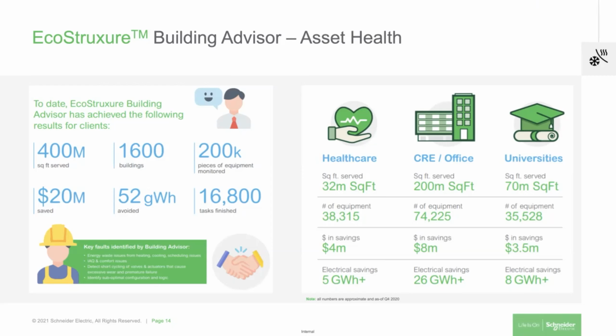Next question: how do you calculate energy savings? Within our fault detection and diagnostics, we have mechanical schedules—the ratings of the pumps, the flow rates, the size of the mechanical assets. We can also take metering data if it's down at asset level. That data is compared against the sequence of operation, and using our algorithms we compare expected control and rates of flow against actual performance. We convert that into a kilowatt-hour calculation and apply the utility rates we have stored for the customer. So it's a mixture of mechanical rating, metering data, and our algorithms and mathematical models that present those savings.